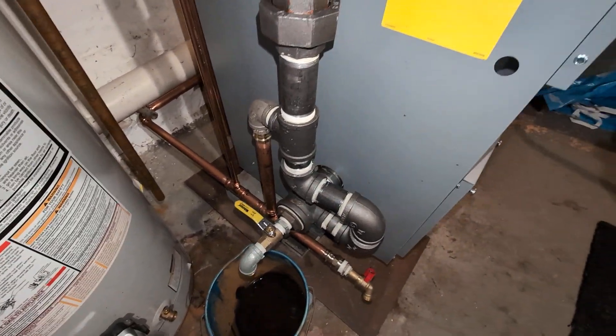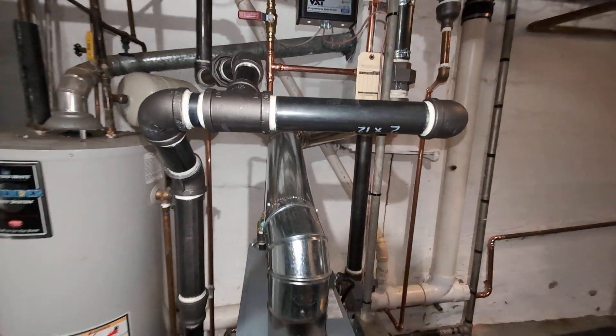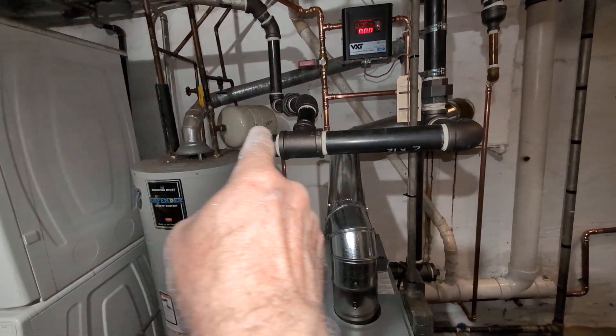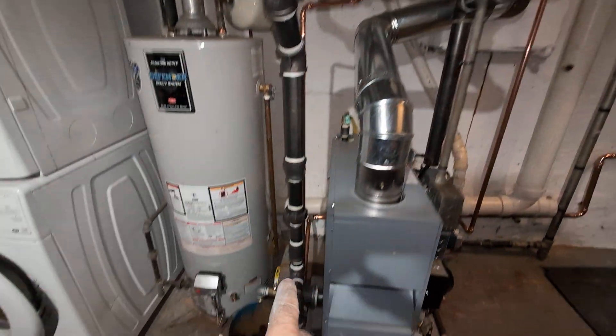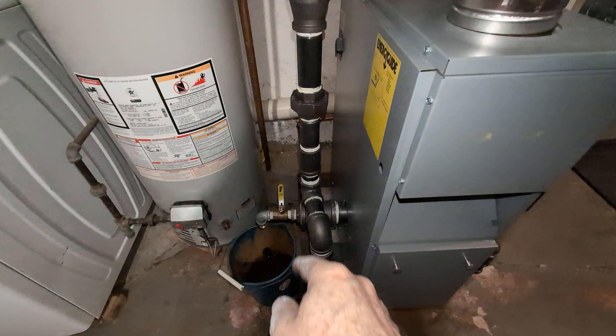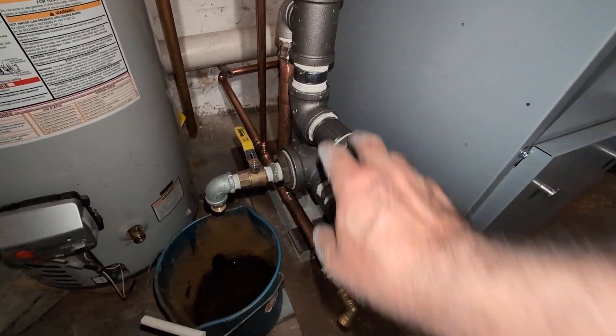And back down the equalizer line to the Hartford loop. I've got this swing joint so if this header expands and wants to move apart, there's the stress relief joint that will allow this movement to occur.